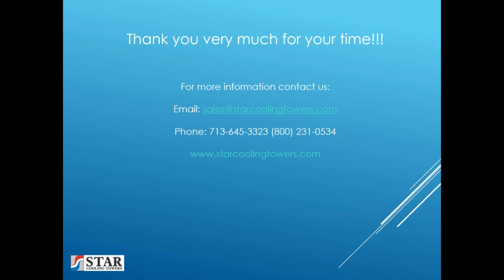And Jim, we have one final question here, and of course, you went through the whole presentation talking about how important inspections are. How often should those cooling tower nozzles be cleaned? Well, at least once a year. I personally would recommend that you look at it every 6 months. The crossflow towers are pretty easy since they're open basins. You can see whether or not you've got problems with the nozzles. You can see if there's nozzles missing or nozzles plugged. Maybe there's accumulations of mud and debris in the basins. And when you see that, you know it's time to clean the basins, which is pretty easily performed.